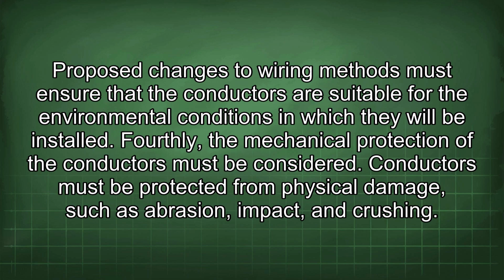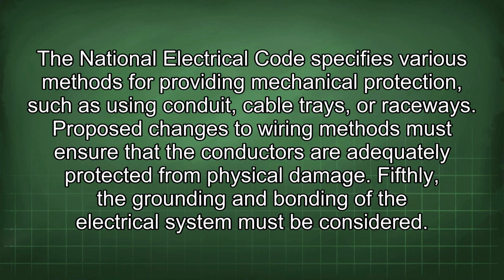Fourthly, the mechanical protection of the conductors must be considered. Conductors must be protected from physical damage, such as abrasion, impact, and crushing. The National Electrical Code specifies various methods for providing mechanical protection, such as using conduit, cable trays, or raceways. Proposed changes to wiring methods must ensure that the conductors are adequately protected from physical damage.